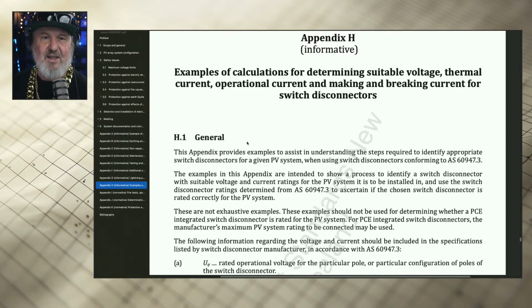And in this standard, we actually have two temperature set points that you need to consider. We've got a 40-degree thermal rating and a 60-degree thermal rating. The 40-degree is for indoors or at ambient temperature, or outdoors at ambient temperature in full shade. And the 60-degree is if you're exposed to solar effects, i.e. the sun shines on your enclosure, on your switchgear. So that means that the thermal ratings drop.